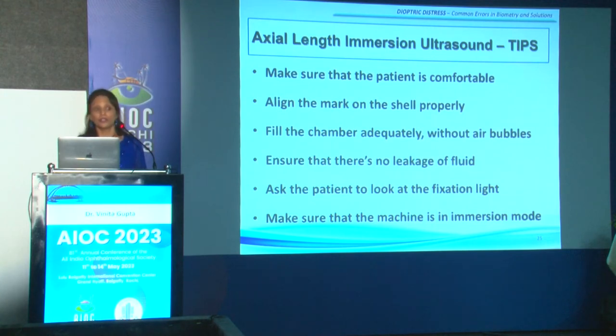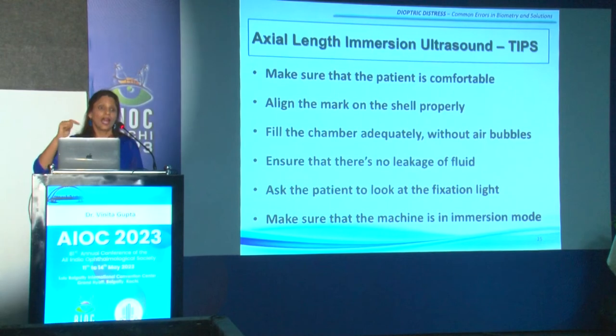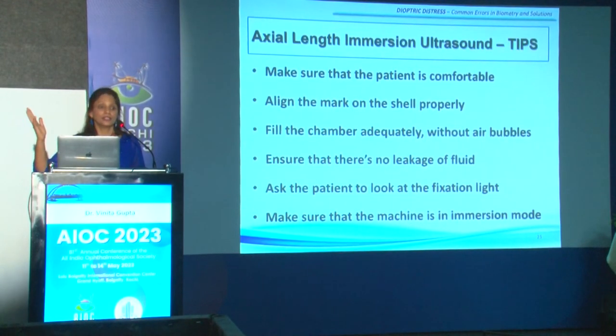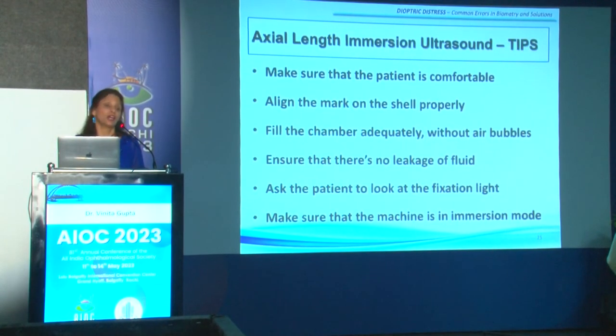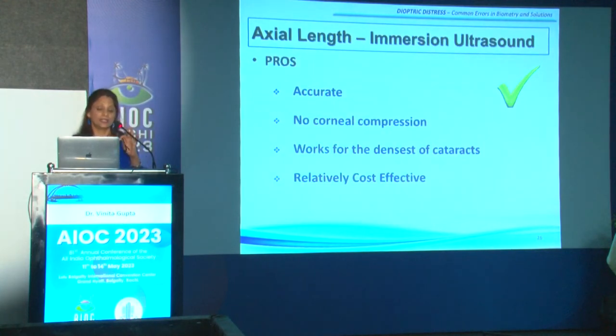This is the most important thing to remember. Many times this happens that if your operator is running it, or if somebody else is measuring, your optometrist is doing a review, he has not changed the mode from the contact mode to the immersion mode. And that will give you erroneous readings, leading to faulty IOL power calculations. And you landing up with a refractive surprise the next day itself.